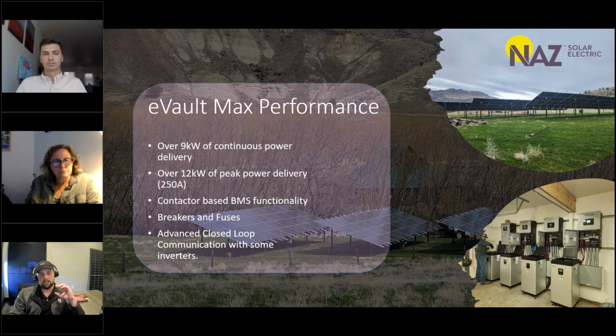I'll segue into this. First of all, there aren't a lot of batteries in the industry that can do 9 kilowatts of continuous load in one package. This battery, at a C/2 rate, can continuously offer 9 kilowatts and peak at 12 kilowatts. So if you're tying this in with, for example, a Sol-Ark 15K, you can use just one battery to feed max power to that inverter in a grid-down or completely off-grid scenario.